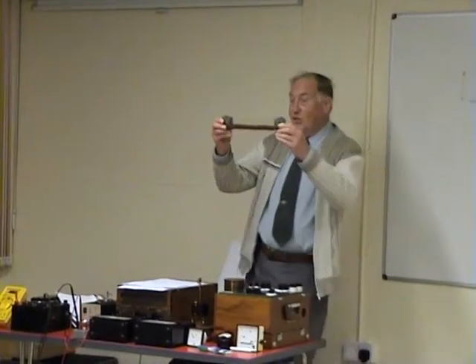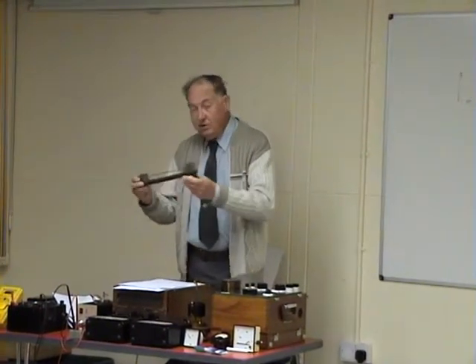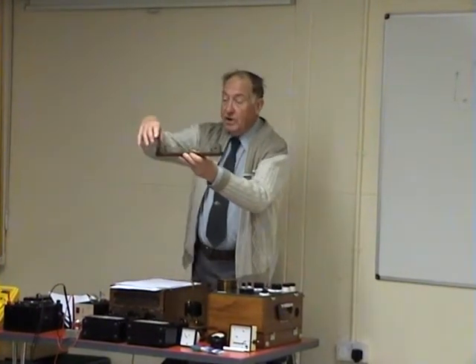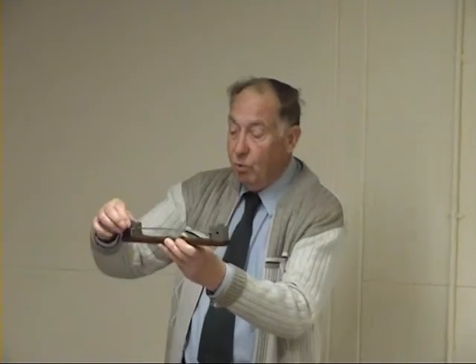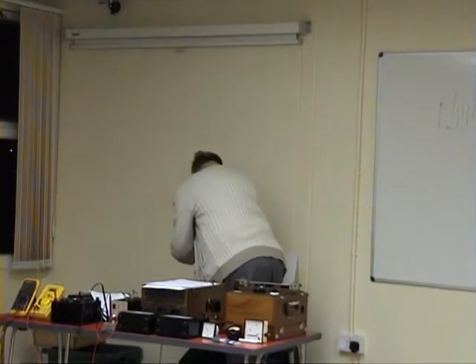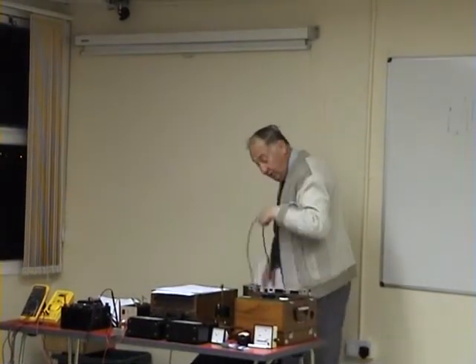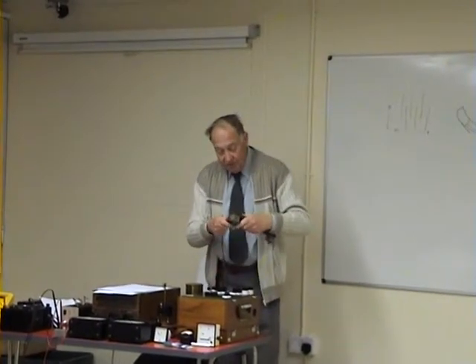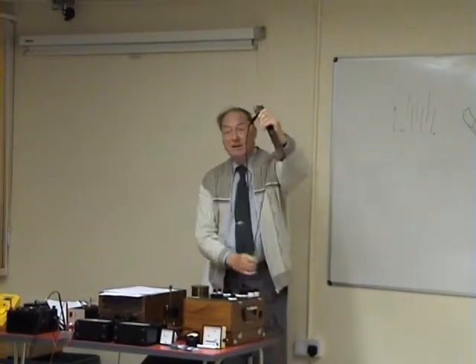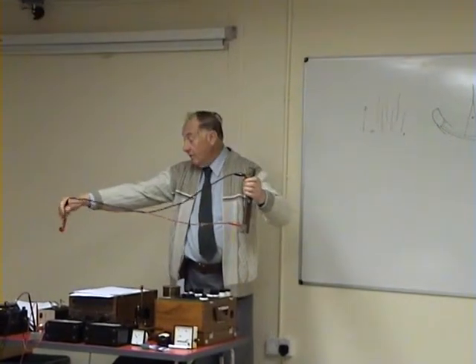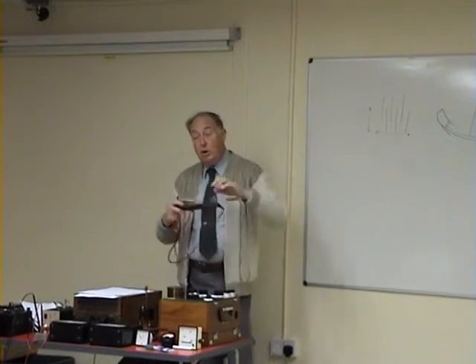And here is an external shunt, the sort of thing that you couldn't put inside the meter. And what you do, remember, to measure current, you've got to break the circuit. So one wire of the circuit goes on there, where that one went, the other one carries on round there, and you connect your test meter to the 2 horns on there. And if you're using Avo leads, it just so happens that those 2 horns are just the right size. Your Avo leads just plug onto them, and that then goes back to the meter. Select the appropriate range, and you can measure high currents using that method.